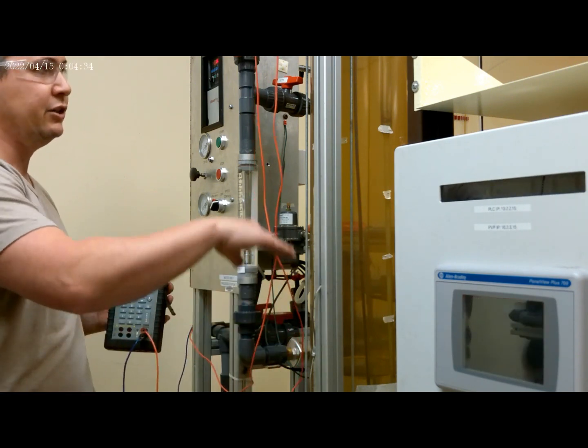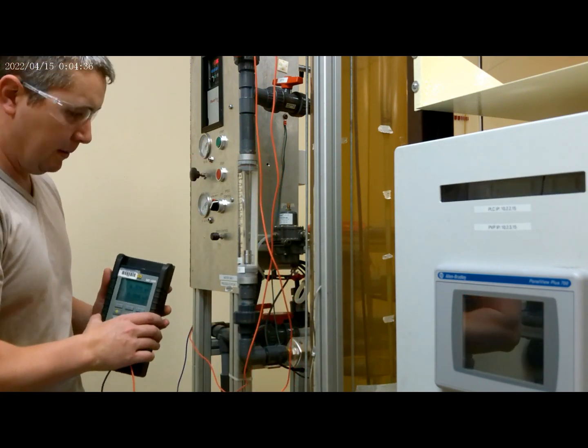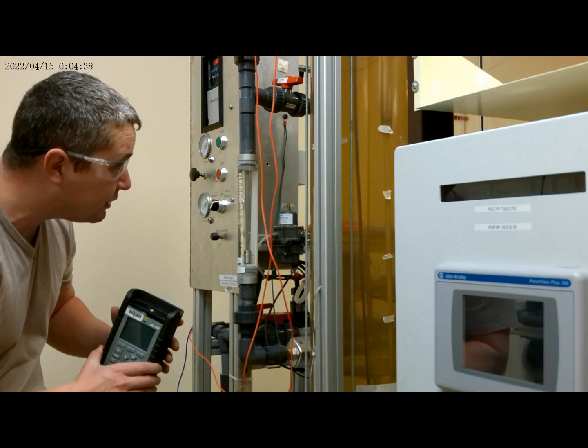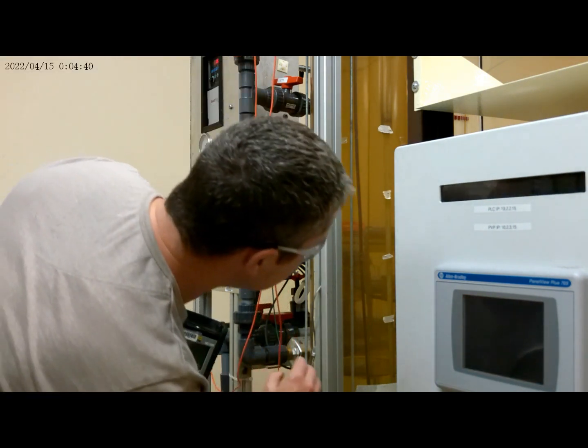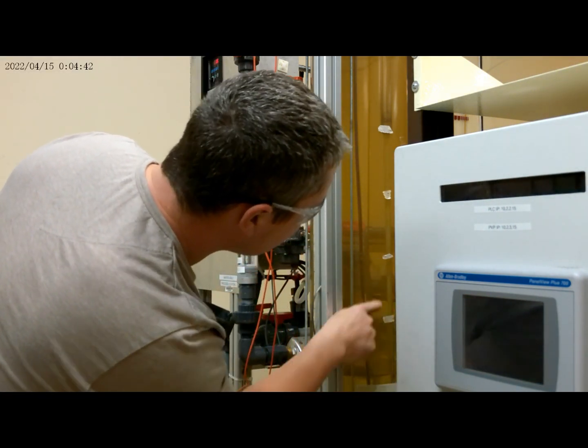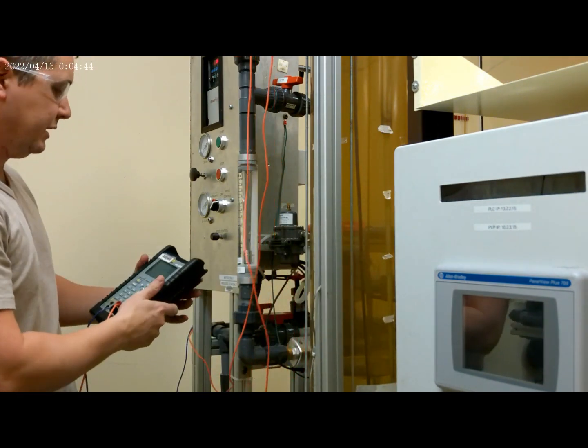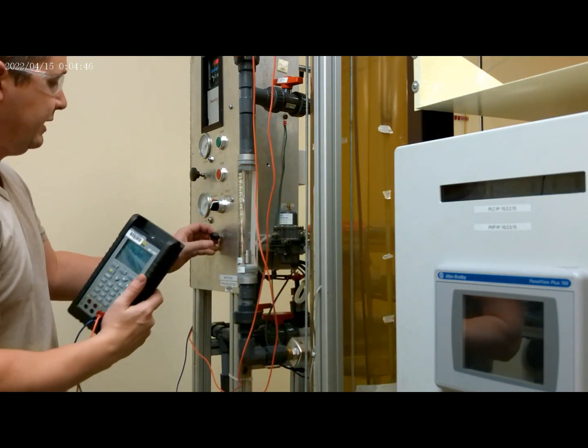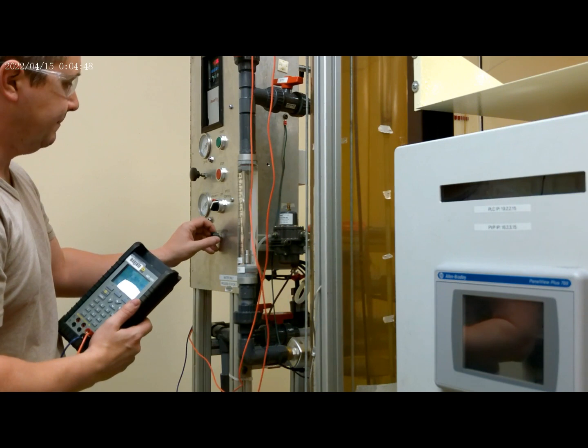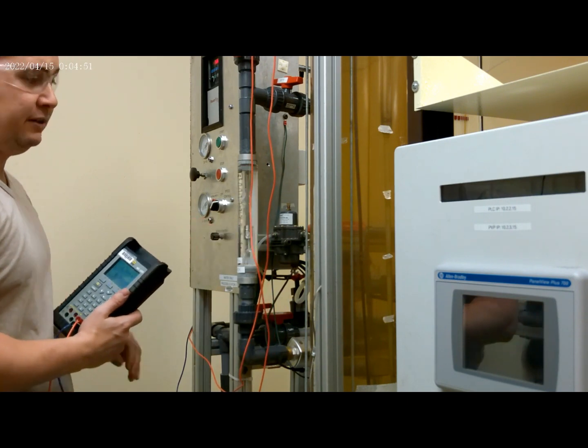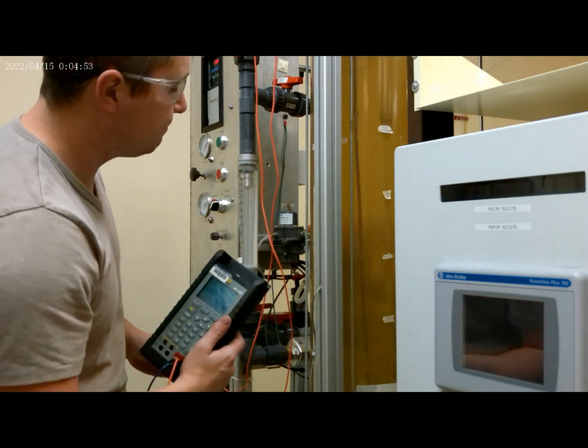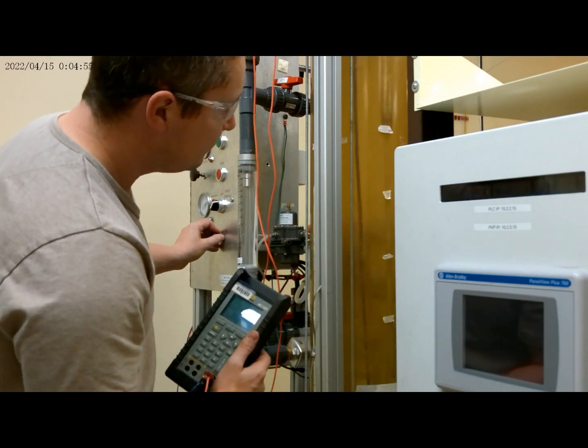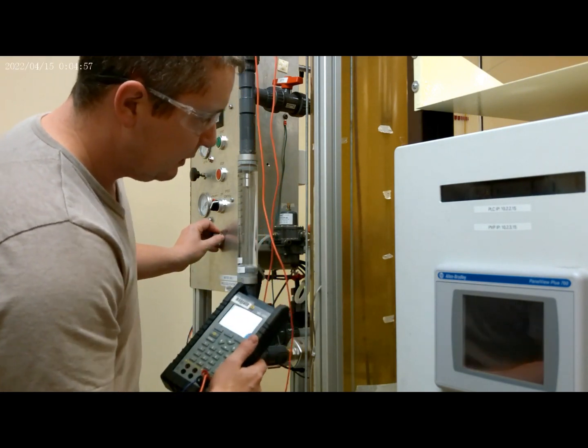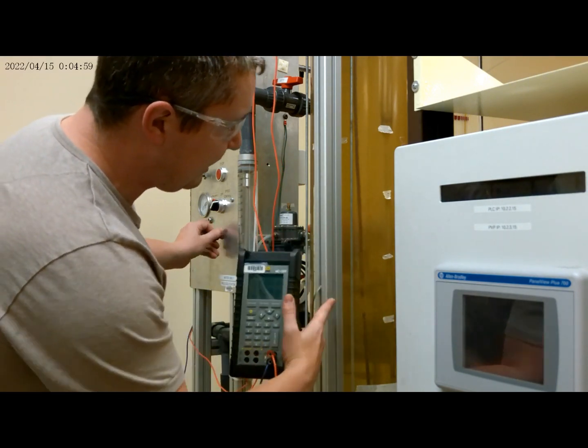Now this is a linear device, so if we go up to 50%, that should give us a 12 milliamp output. Let's try that. Let's start up our variable frequency pump and drive this up. Now you see all the splashing of the water.